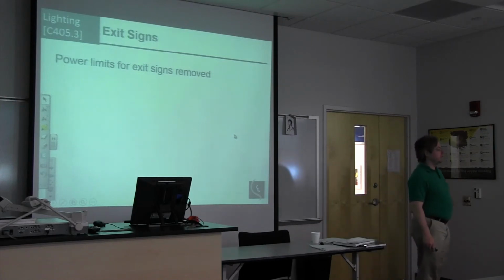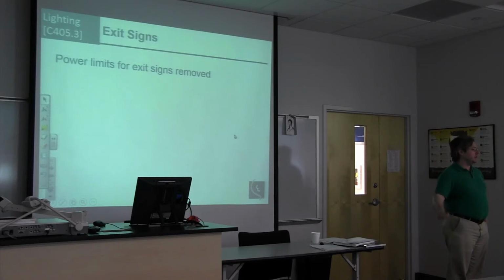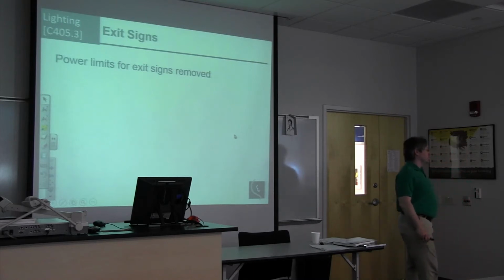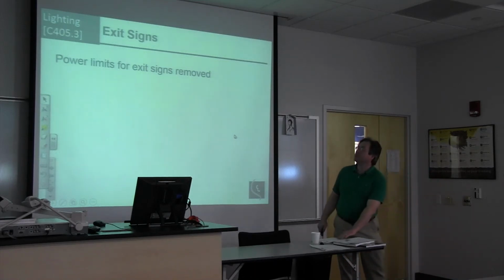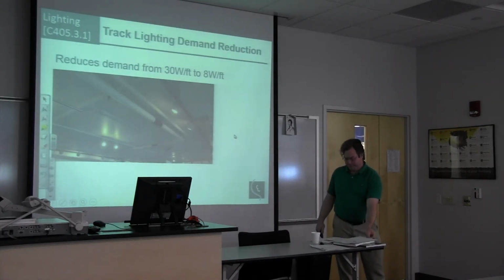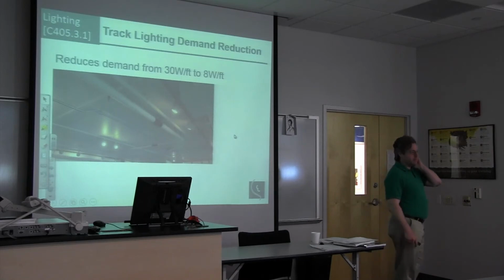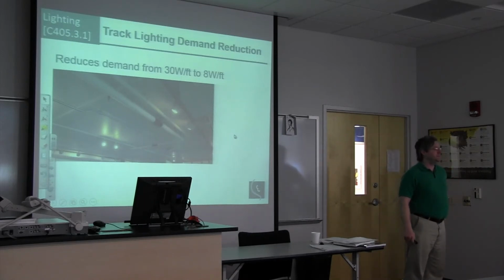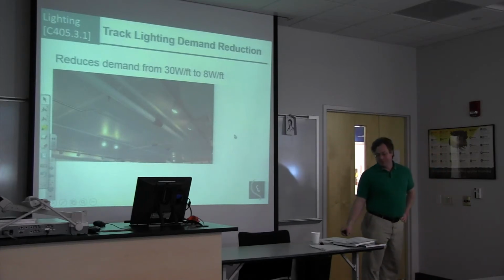Exit signs, power limits have been removed from the code. I think this is predominantly because everyone's gone to LED. And the difference between the best LED exit sign and the worst one is almost nothing anymore. So they looked at it and said, having this code requirement, it's not even doing anything anymore. Track lighting goes from 30 watts per foot down to 8 watts per foot. Mostly because everyone's putting up LED and fluorescent track lighting now. So this can help for your lighting power density calculations, because before, if you used any track lighting, it would really kill your calculation for you.